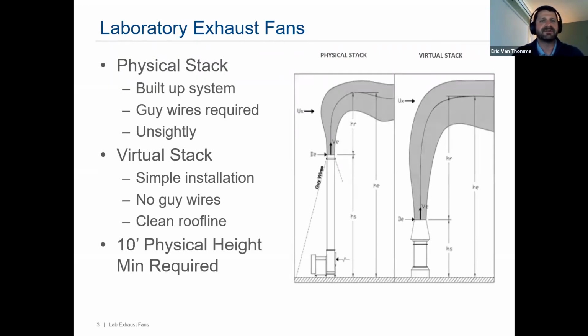So we'll touch briefly on two different types of laboratory exhaust fans. You've got two options: the physical stack, which is the traditional style where you've got a house centrifugal blower mounted on the roof, or maybe down in a penthouse just below. And then a physical stack. It's a built-up system. Typically, that stack is pretty tall, and so you're going to have guy wires tied back to the roof deck. Typically, it is going to create an unsightly look, but is effective for exhausting laboratory exhaust fumes. Something that's been newer and popularized by fan manufacturers over the last probably 15 to 20 years or so is really the virtual stack.